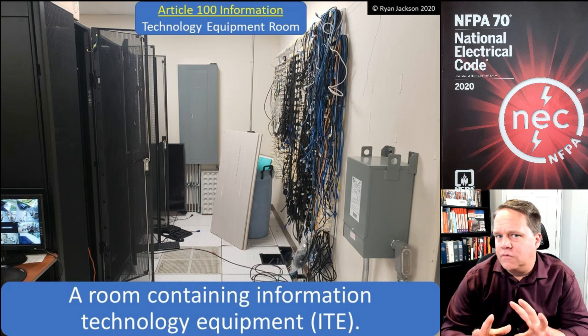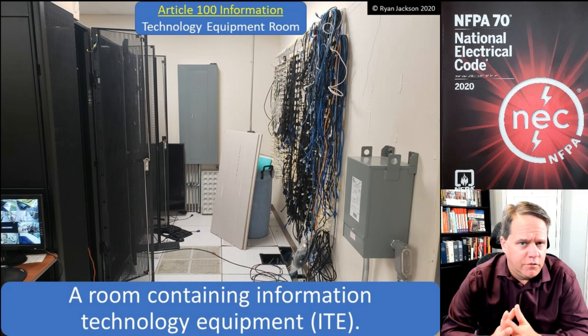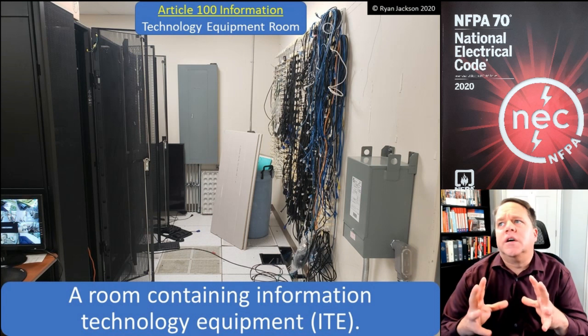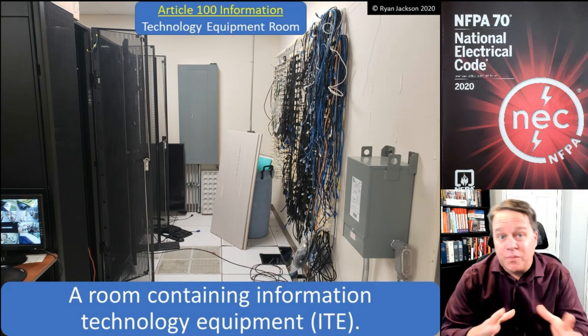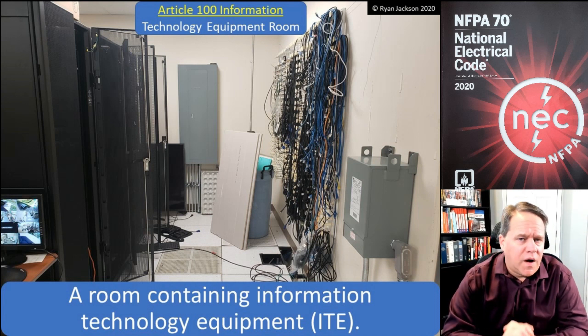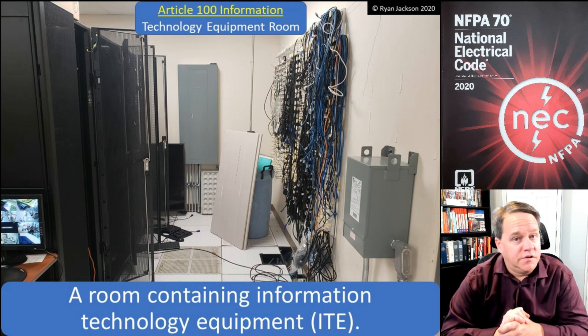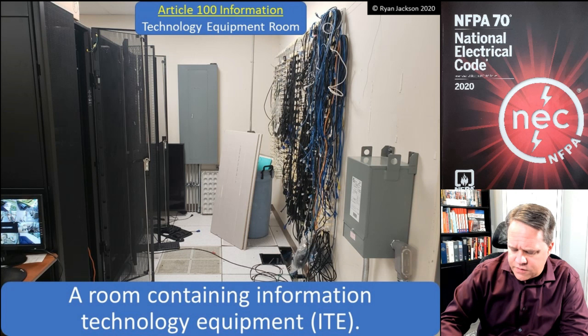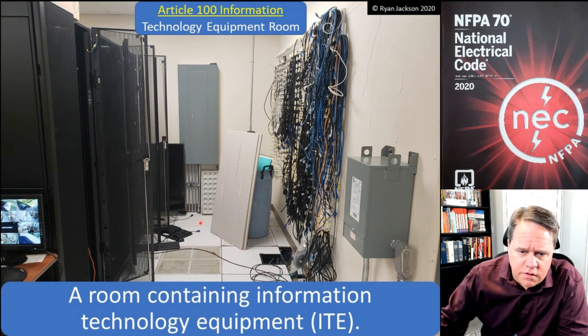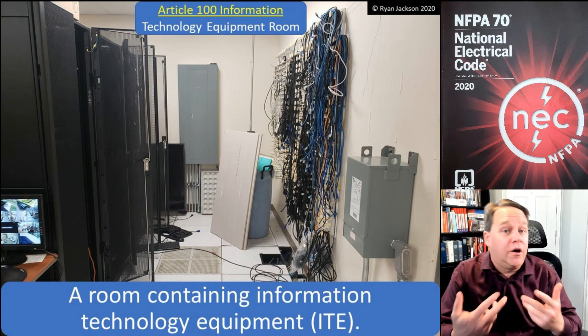Article 645 is one of the more obscure topics in the NEC. It covers IT rooms and historically has been kind of an optional code article. What Article 645 really does is allow different wiring methods underneath the raised floor. Notice in this photograph that the floor has removable tiles and a grill opening.